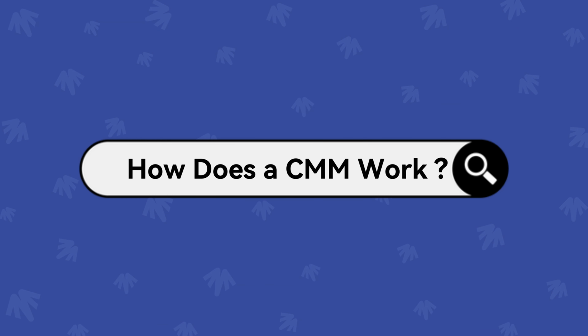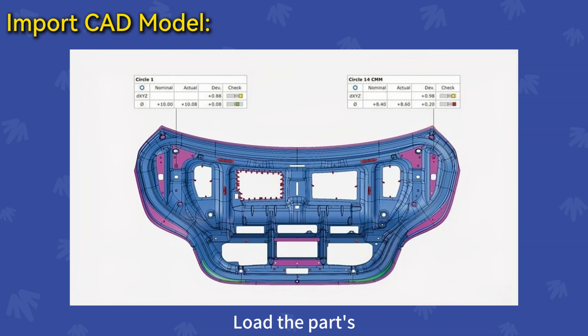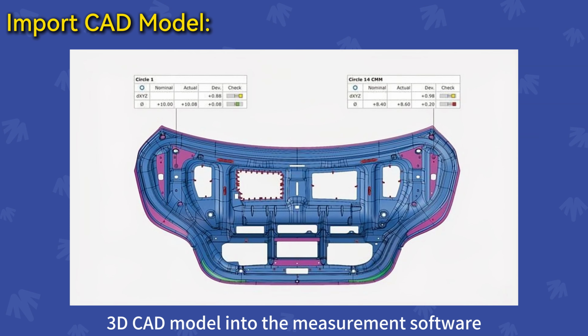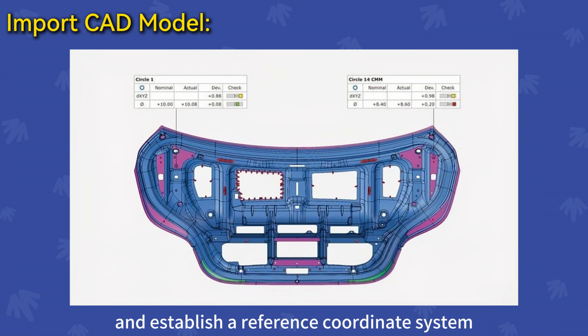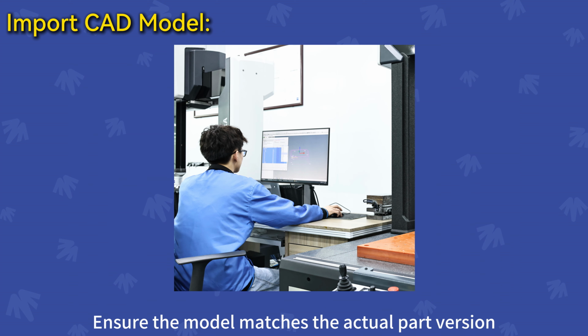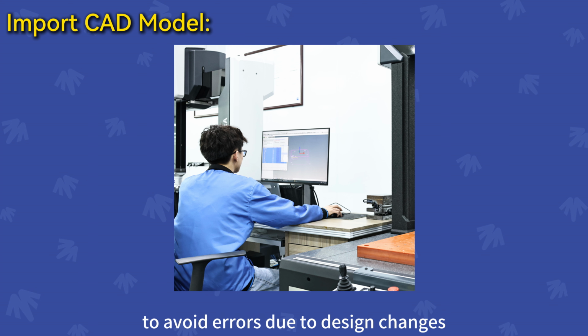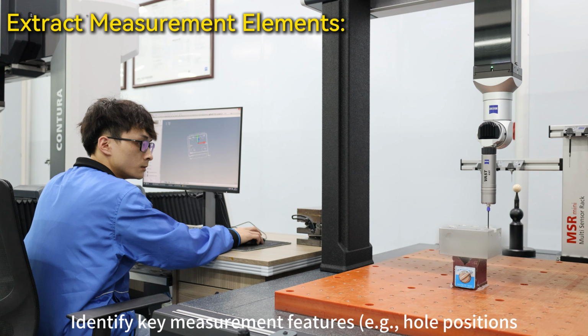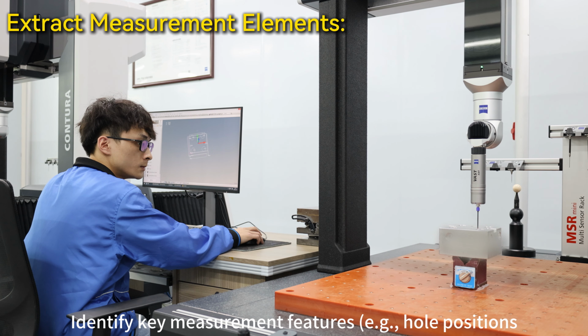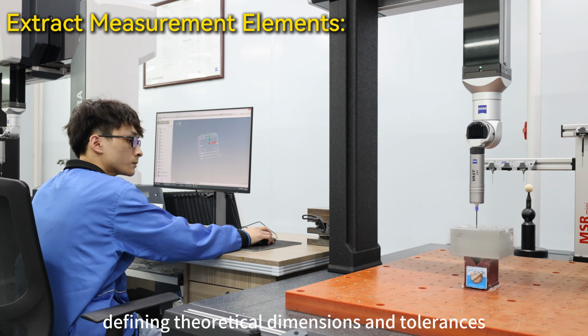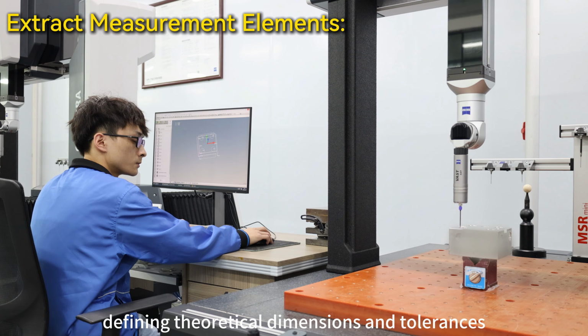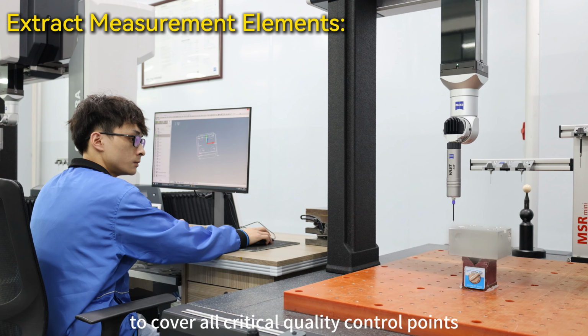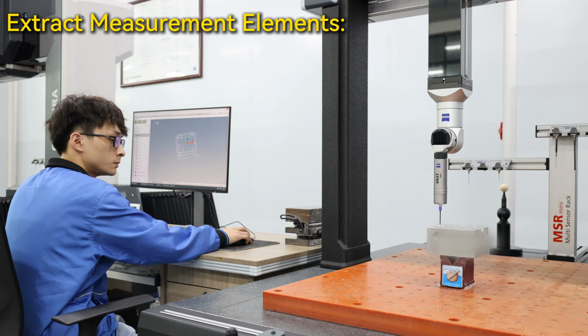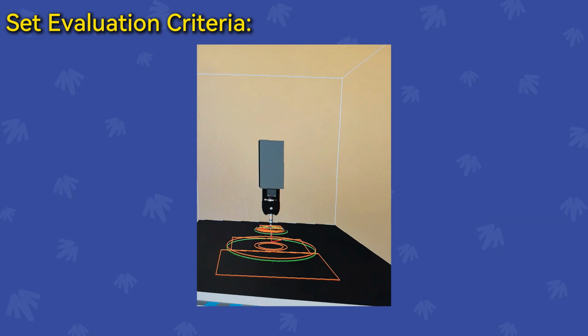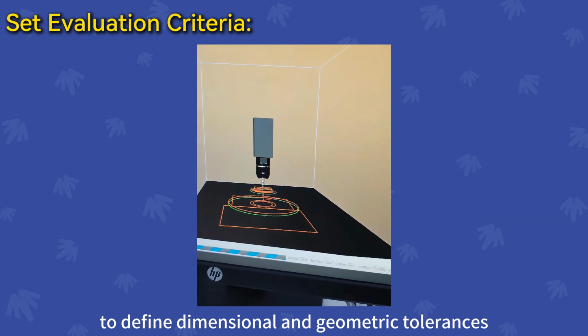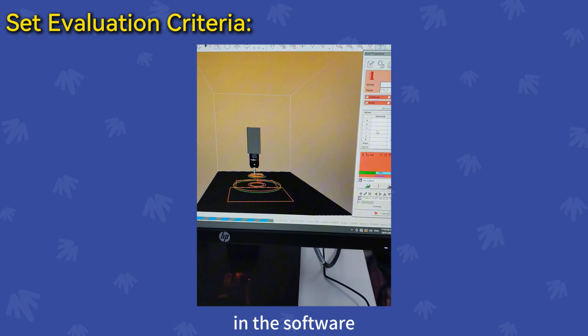How does a CMM work? Import CAD model. Load the part's 3D CAD model into the measurement software and establish a reference coordinate system. Ensure the model matches the actual part version to avoid errors due to design changes. Extract measurement elements. Identify key measurement features, e.g. hole positions, planes, contours, from the CAD model, defining theoretical dimensions and tolerances. Plan probe point distribution to cover all critical quality control points. Set evaluation criteria based on 2D drawings. Refer to engineering drawings to define dimensional and geometric tolerances in the software.